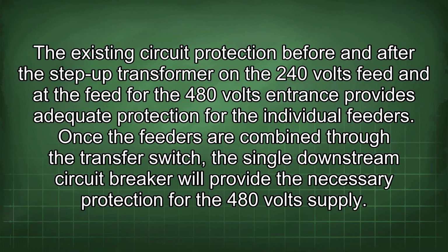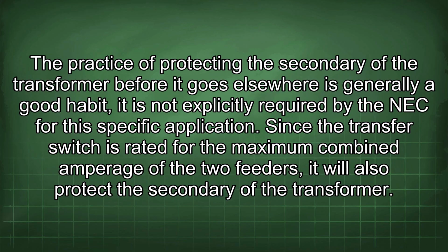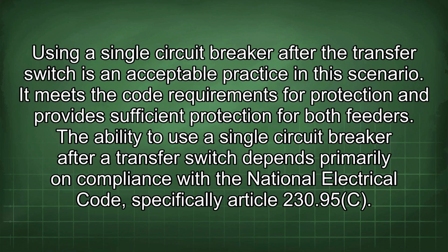Once the feeders are combined through the transfer switch, the single downstream circuit breaker will provide the necessary protection for the 480 volts supply. The practice of protecting the secondary of the transformer before it goes elsewhere is generally a good habit. It is not explicitly required by the NEC for this specific application. Since the transfer switch is rated for the maximum combined amperage of the two feeders, it will also protect the secondary of the transformer. Using a single circuit breaker after the transfer switch is an acceptable practice in this scenario. It meets the code requirements for protection and provides sufficient protection for both feeders.